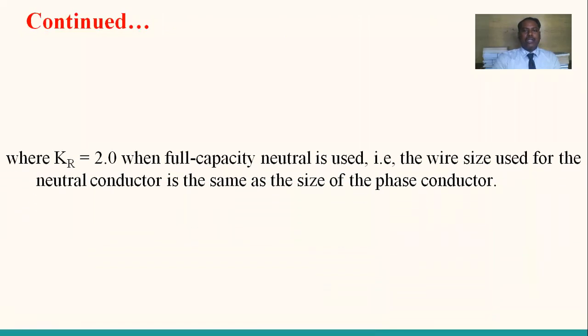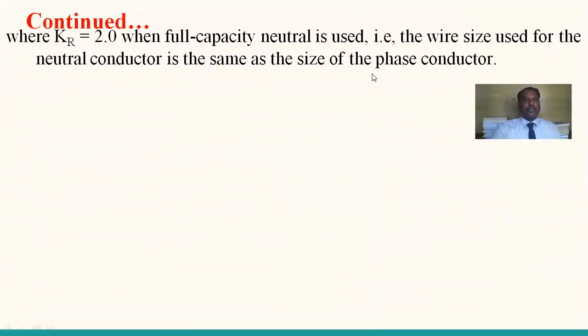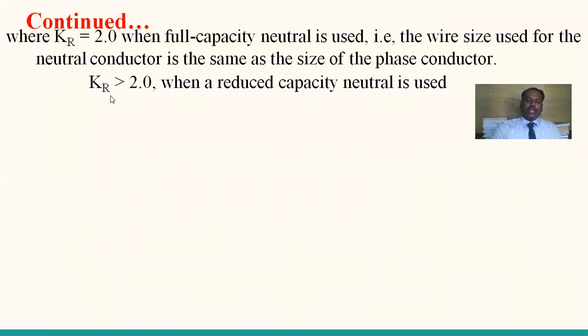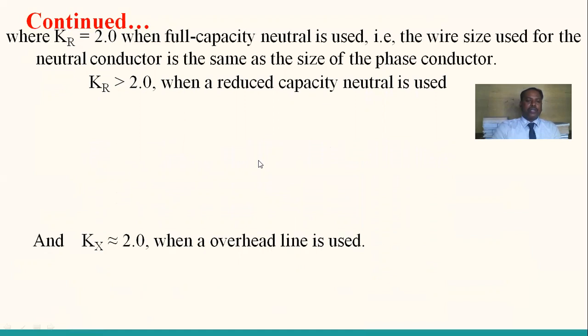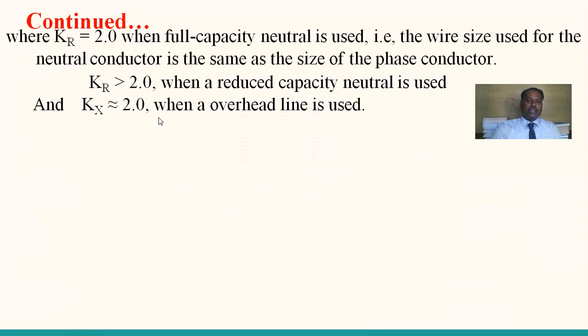Now you see here, Kr and Kx were already defined in the earlier case as the conversion constants. Kr is equal to 2 when a full capacity neutral is used. And what is a full capacity neutral? The wire size used for the neutral conductor is the same as the size of the phase conductor. That is known as the full capacity neutral. Remember, students? What do you mean by full capacity neutral, and what do you mean by reduced capacity neutral? A full capacity neutral is one where the size of the neutral conductor is the same as that of the phase conductor. When a full capacity neutral is used, the Kr value is equal to 2. Kr is greater than 2 when a reduced capacity neutral is used. And Kx is approximately equal to 2.0 when an overhead line is used.